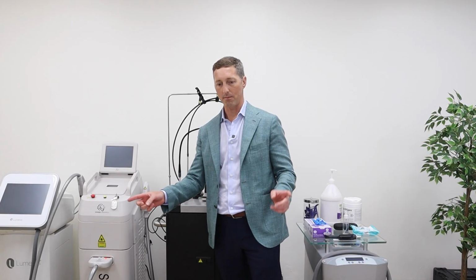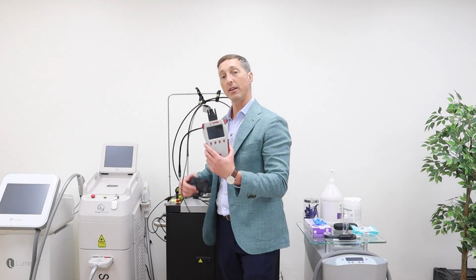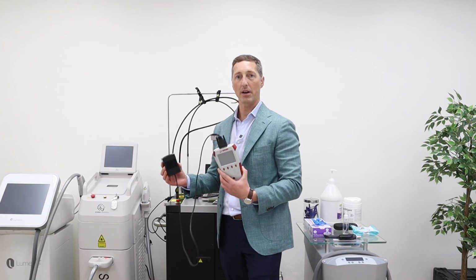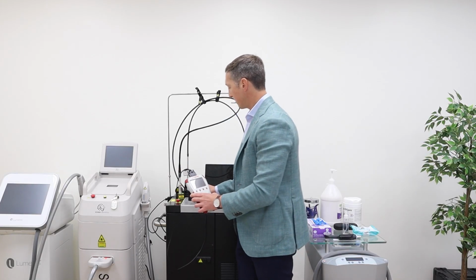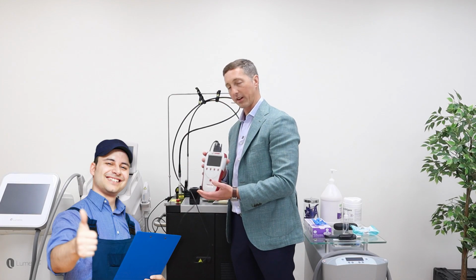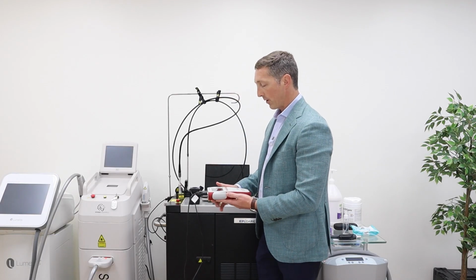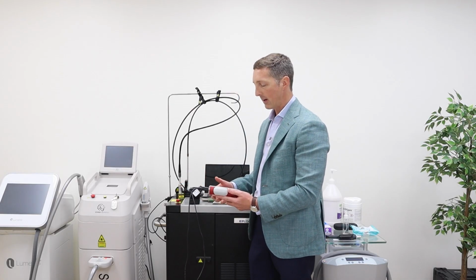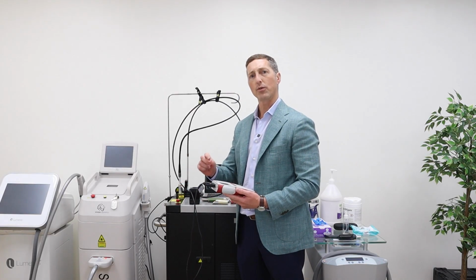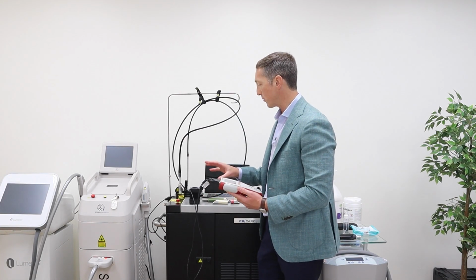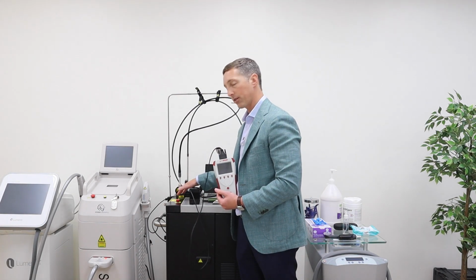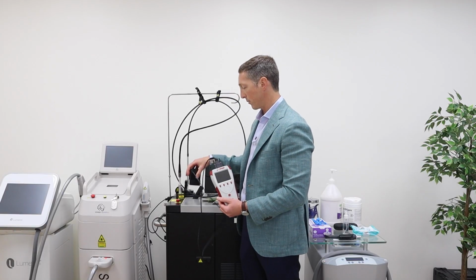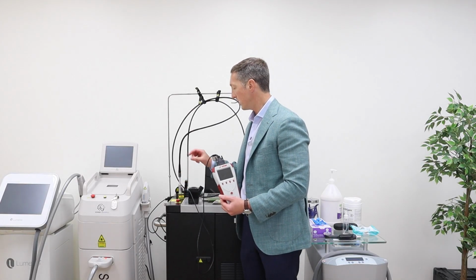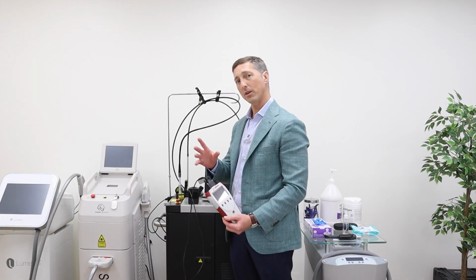But it doesn't answer the question, how does one system equal the other? To do that, we need to do an independent external calibration verification. And this is where once a year, you're going to have a technician come out with an external calibration meter. Now, it's important to understand when this calibration meter was also last checked. It should be within 18 months, a year and a half, and that will allow you to have what's called traceability. So that is to say, you need a written record as to when your system was externally checked or verified and when this was externally checked or verified to really ensure that this is correct. So far, so good? Right.